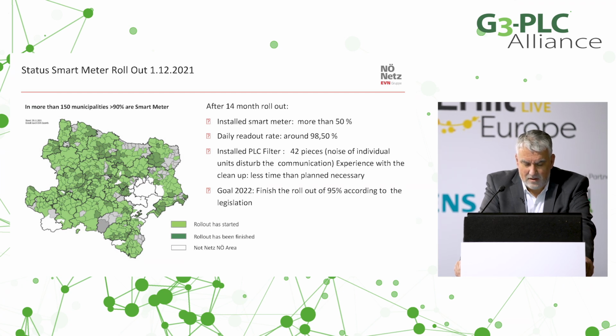When we have a problem with the communication, when we have too much noise maybe, in some cases we install filters at our customers. You see we have more than 400,000 meters installed, and at the moment we need only 42 filters. In general, our experience with the cleanup, to see if all meters communicate in a substation area, is that we need less time than we planned at the beginning of the project.